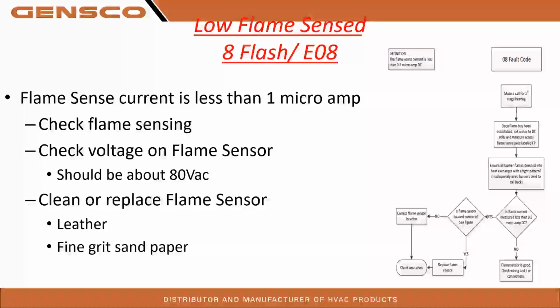So low flame sense, an 8 flash or an E08. So we're giving you a very good callout of troubleshooting flow charts here. We talked about flame rectification. So we're sensing flame current less than 1 microamp. We have to check voltage on the flame sensor, which should be around 80 volts. So I guessed right there. I remembered right anyway: 80 volts at the flame rod prior to lighting. So we're going to clean or replace the flame sensor. Leather, fine grit sandpaper, a dollar bill works fine.